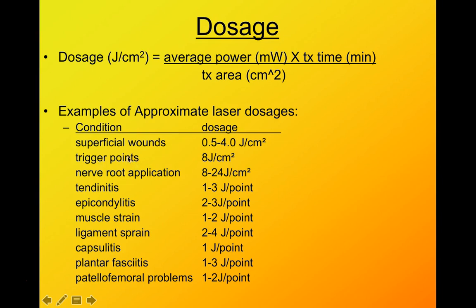Trigger points, we could use that probe. So this would be 8 joules per centimeter squared if you're using more of a cluster. It could also just be 1 joule per point, you typically see as well. Nerve roots, again, if you're using a probe, it would be really like 1 to 3 joules per point. If you're using the cluster, it's more of the 8 to 24. So just some typical examples of things there.